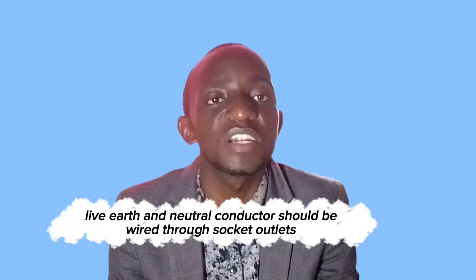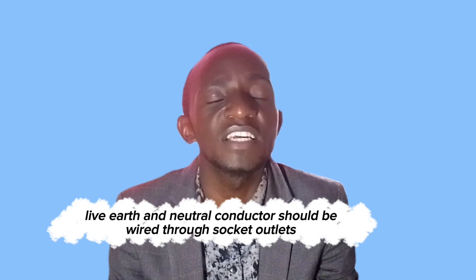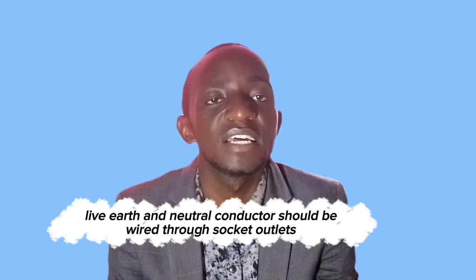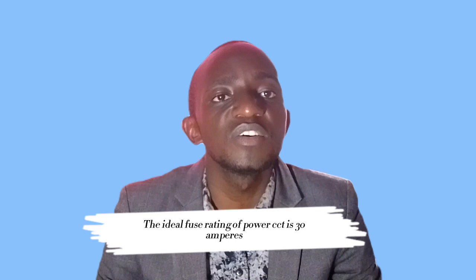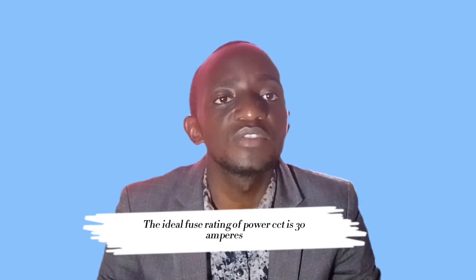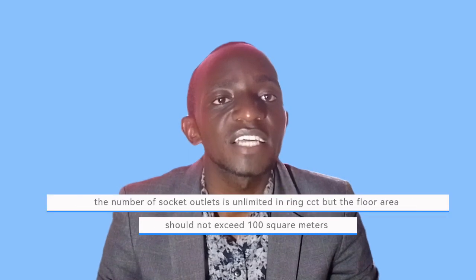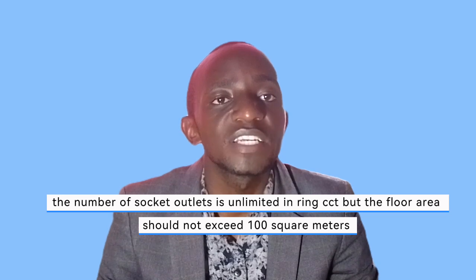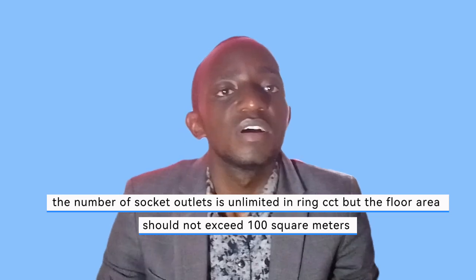Number 2, the ring and radial circuit, the power circuits should run live, neutral and earth conductors to each and every socket outlet. Number 3, the fuse rating of a ring circuit and a radial circuit should be 30 amperes. Then number 4, this is especially for ring. You can connect unlimited number of socket outlets in a ring circuit, but the floor area should not exceed 100 square meters. Those are the IEE regulations regarding power circuits.